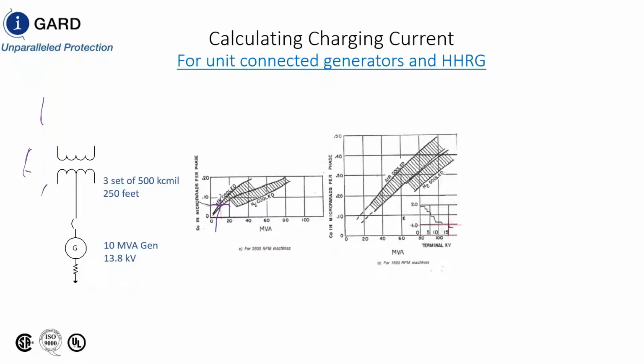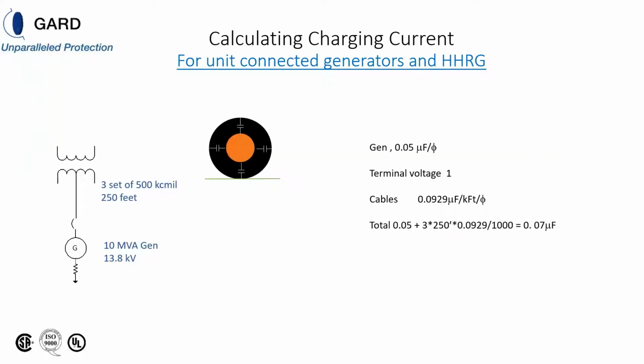I don't know if you guys remember the T&D, Westinghouse put out a T&D book. This came out of that chapter in the T&D book, as well as ABB probably put out another book that reduplicated that. So the terminal voltage is a multiplier of 1. The generator is 0.05 microfarads per phase, according to this chart.